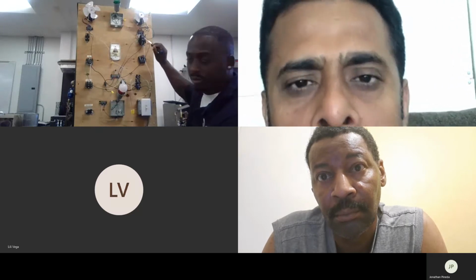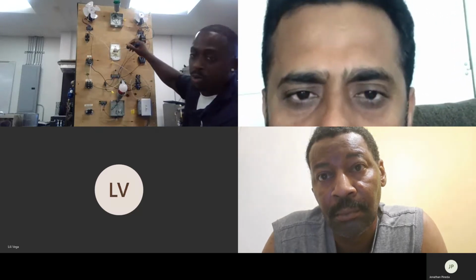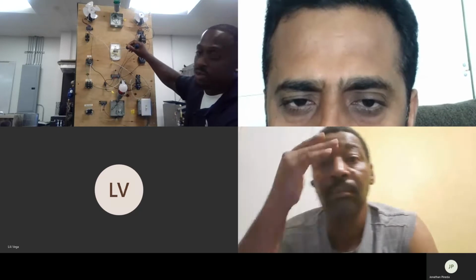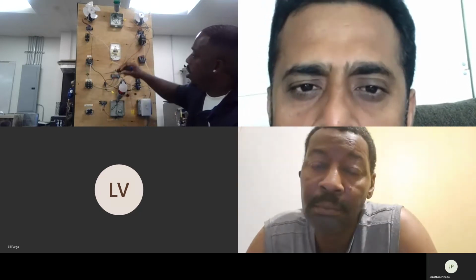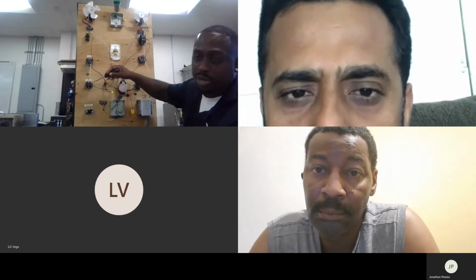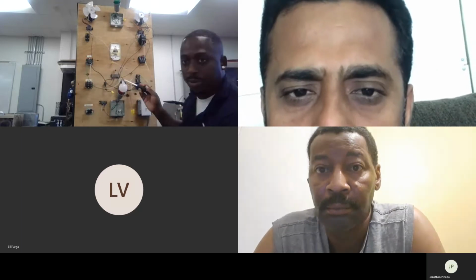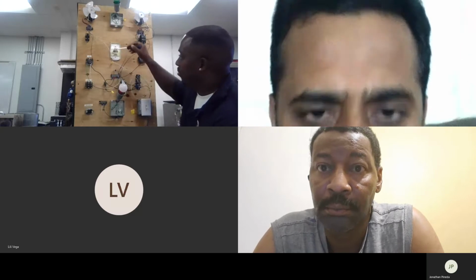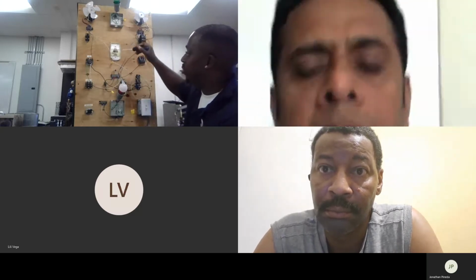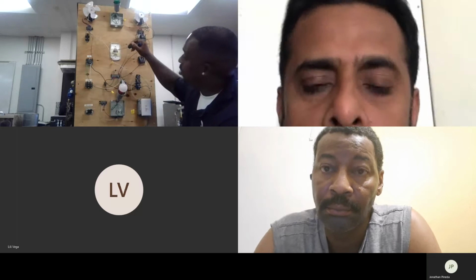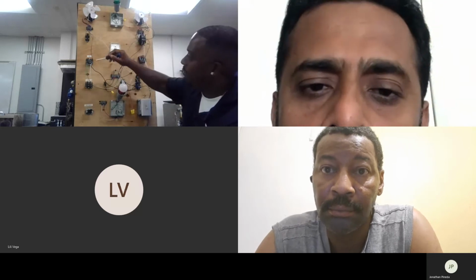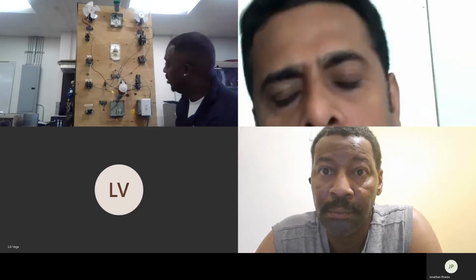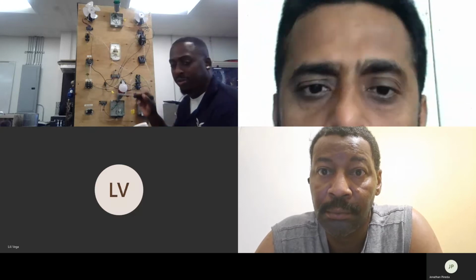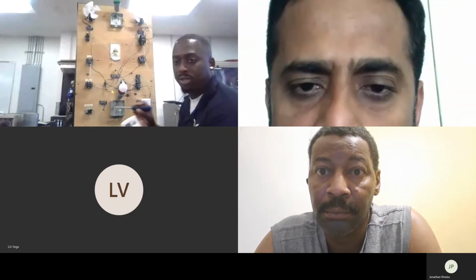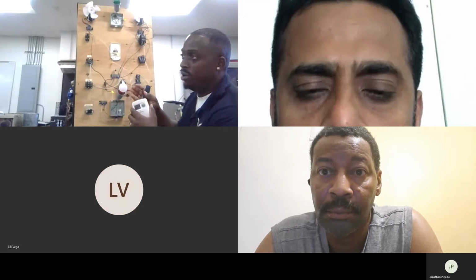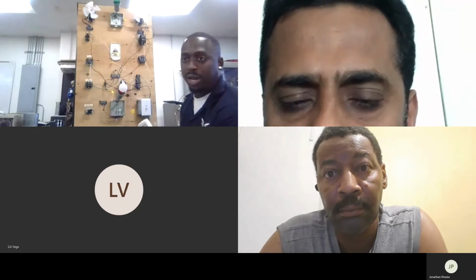So even if this W wire wasn't white, we know it's W, so it better be connected to our relay 2 coil, which controls our heat, from last week when we were doing heat. And if this G wire was black instead of green, it doesn't matter — we know it's G, so it has to be connected to our fan relay coil to operate the fan. That's the whole point of those different designations, so you know how to identify each circuit, and that helps you make sure your unit is wired up correctly.